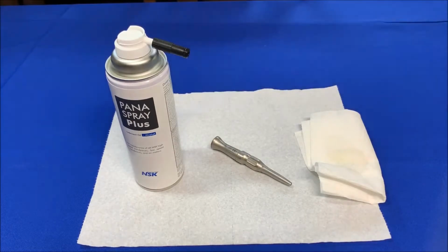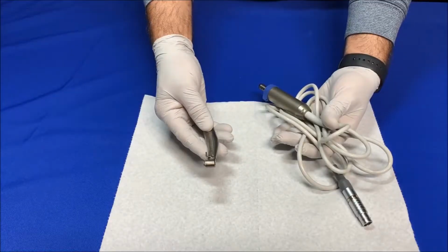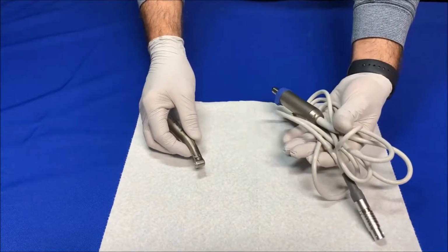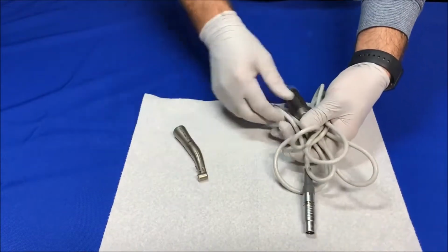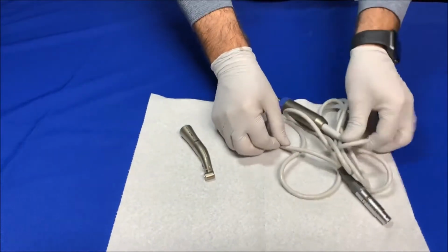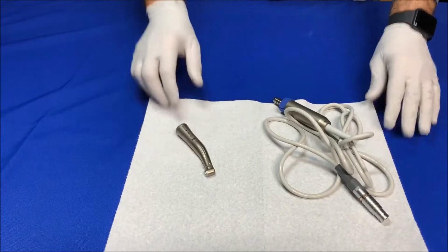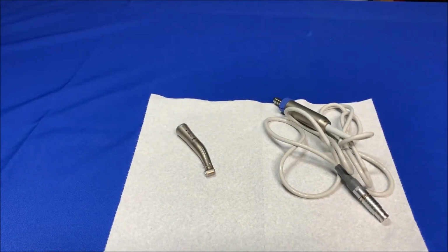The entire motor and its cord is autoclavable, and so is the attachment. But the motor and the cord do not need to be lubricated. Place the handpiece and the micromotor in separate autoclave pouches and seal them before putting them into the autoclave.